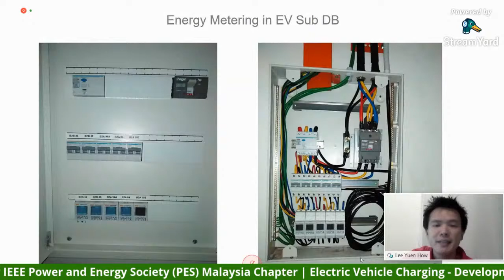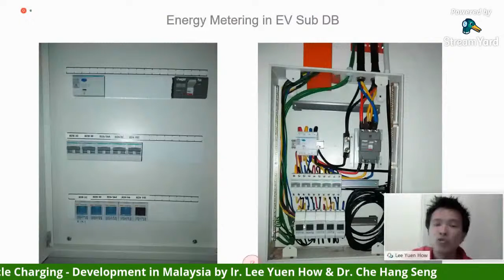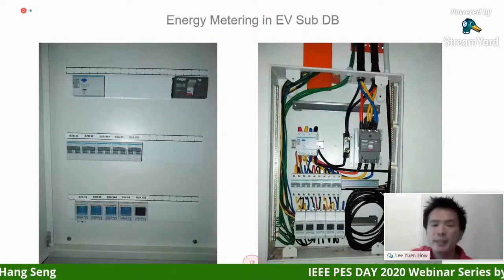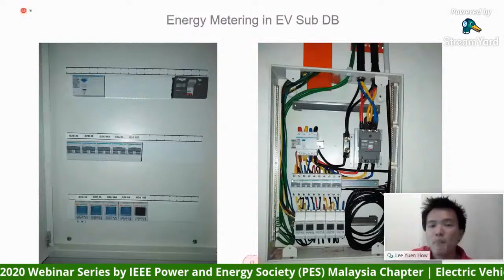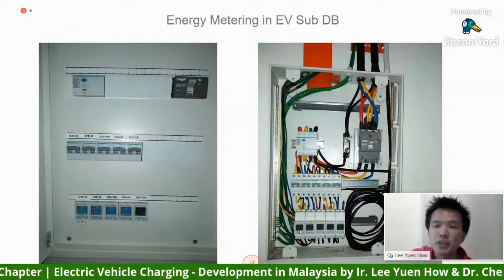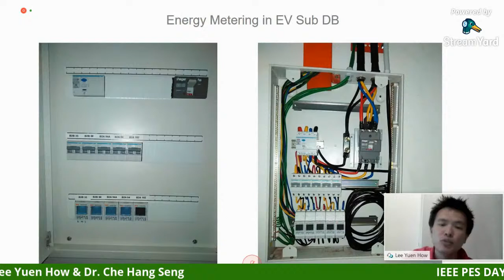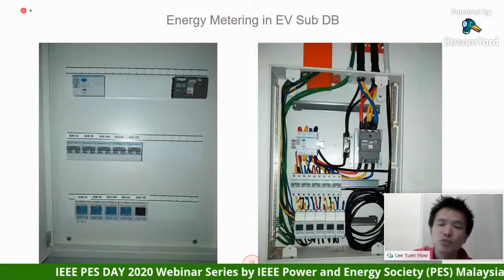Each EV DB will need individual protection with an MCB and an energy meter to measure energy consumption by the owner. If they don't pay, you can switch off the breaker supplying power to their designated car park area. The energy meters can be hooked up to an energy management system where the admin can monitor monthly usage without going to each DB or meter to record it manually.